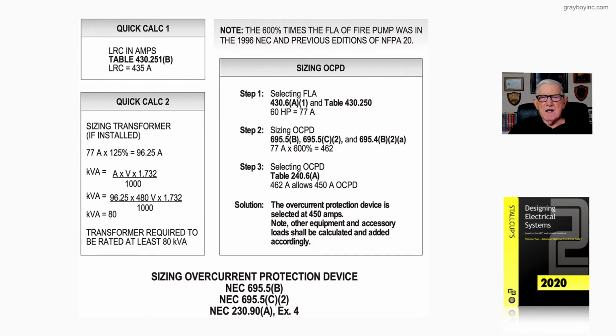Now, to select the size overcurrent device, we always have to round up in this case because we want the overcurrent device to hold until fire pump failure. So step 3, we would look at 240.6(A), and 462 amps would allow us to use a 450 amp overcurrent device there, so it requires. Now, the overcurrent protection device is selected at 450 amps.